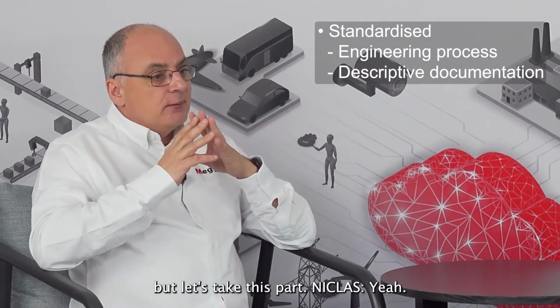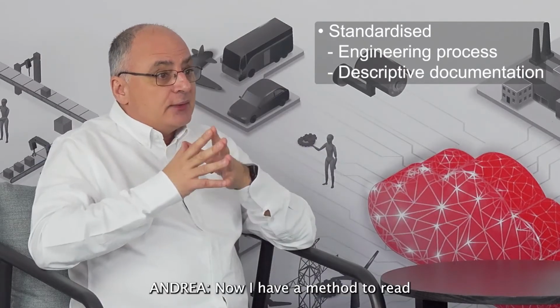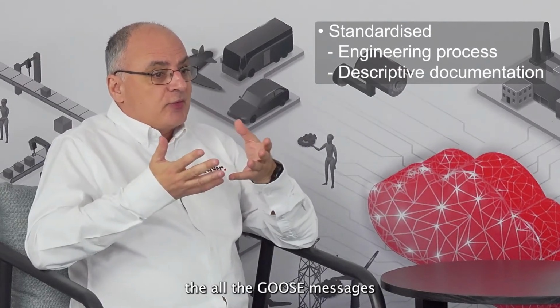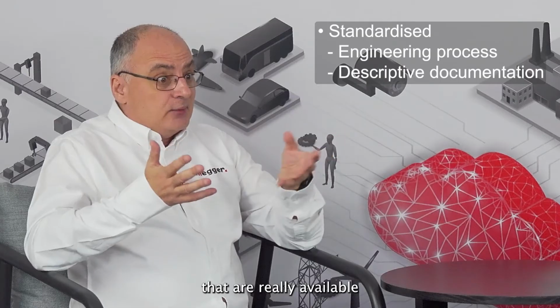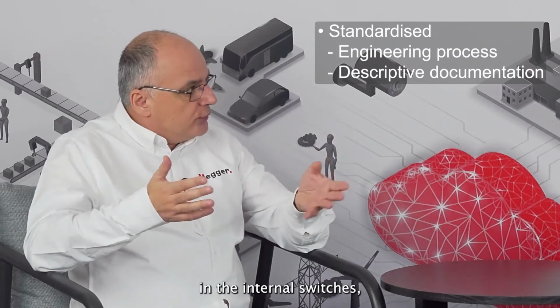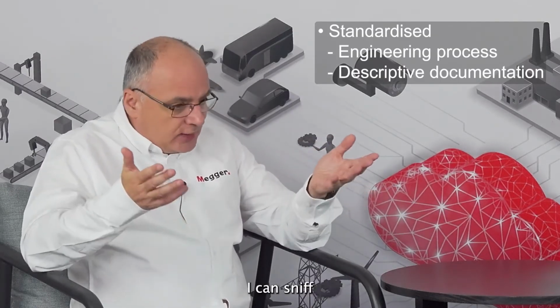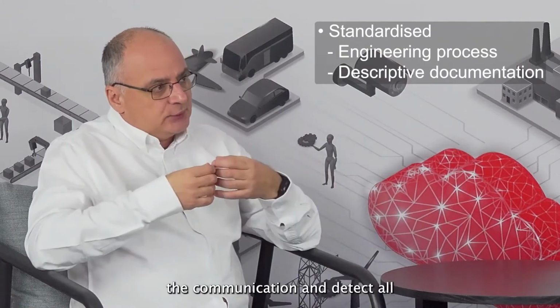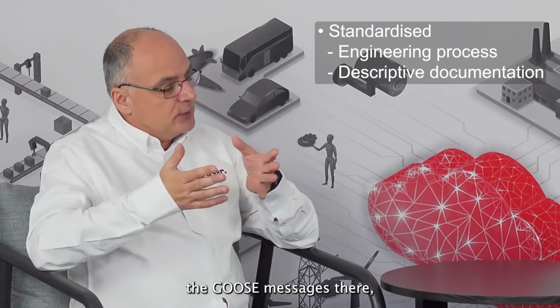Now I have a method to read all the goose messages actually available on the network, in the Ethernet switches, in the fiber optics. I can sniff the communication and detect all the goose messages there.